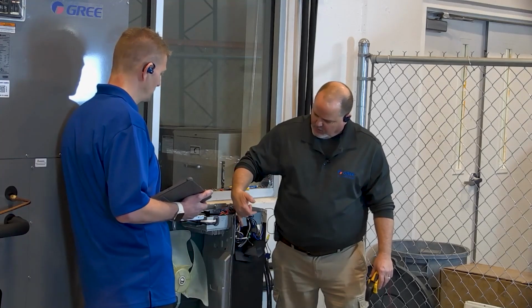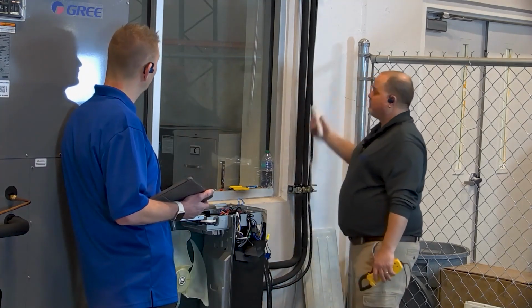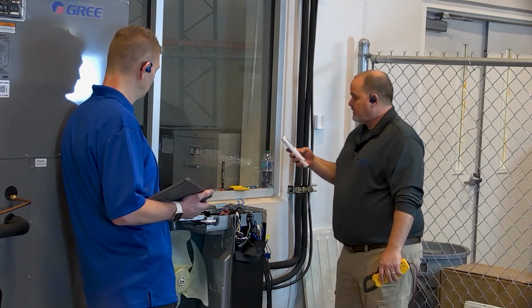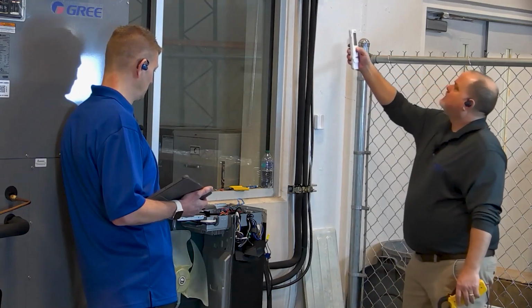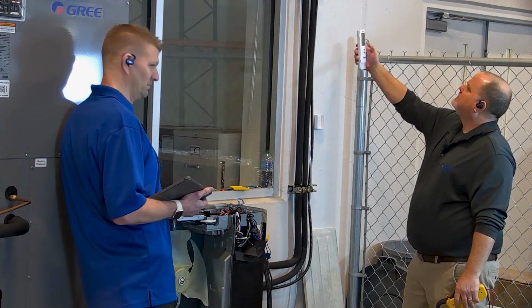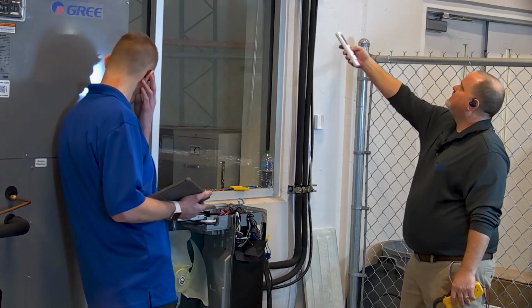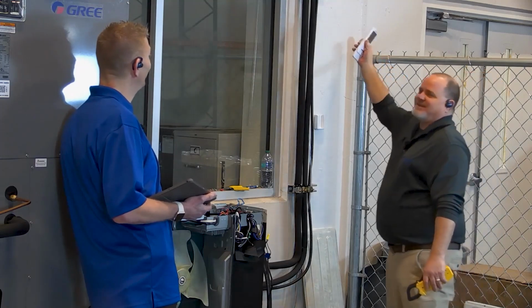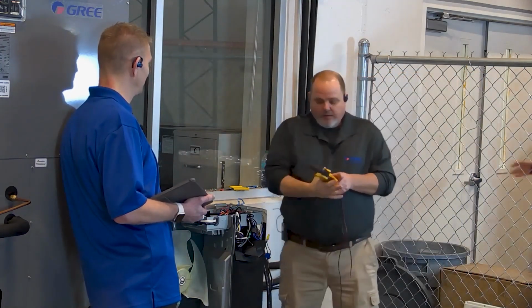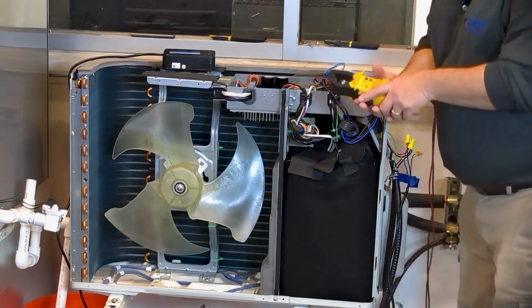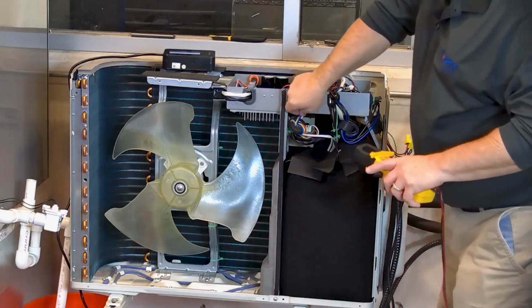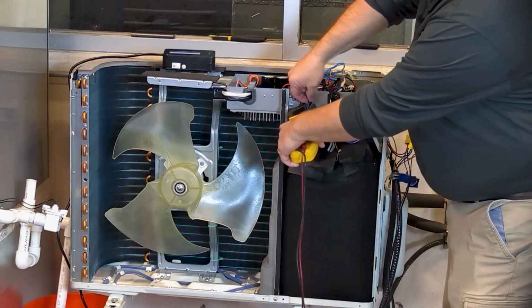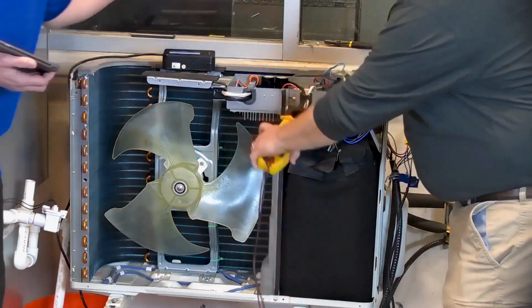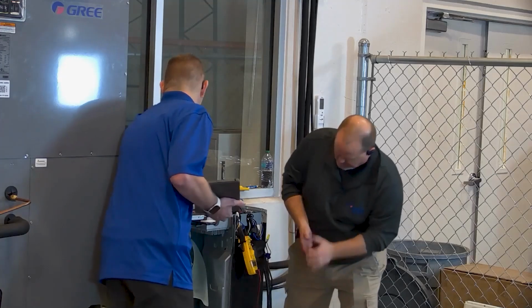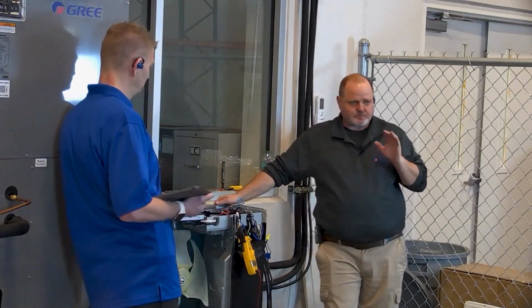So coming off the top here, you can see them here. You've got yellow, blue, and red going to my compressor, and I've got to get this off of fan mode and actually put it on a mode. So we'll put it on heat mode. Not familiar with this remote. I don't think I can get it. Well, maybe I can. They don't give me much room here. There we go. All right. So I got the amp probe hooked up. This machine should be coming on in a minute.